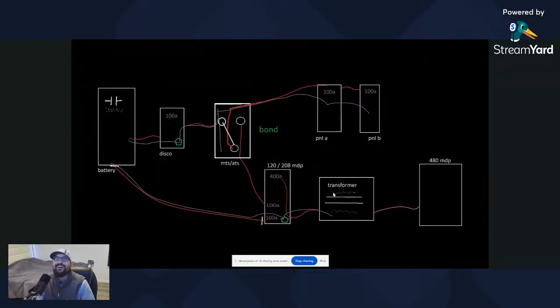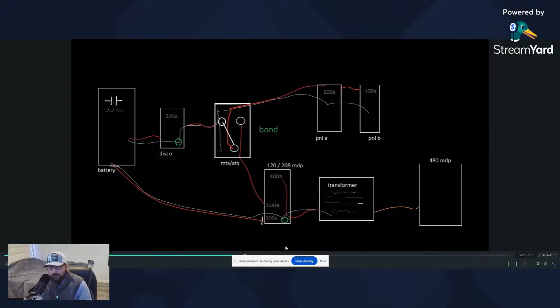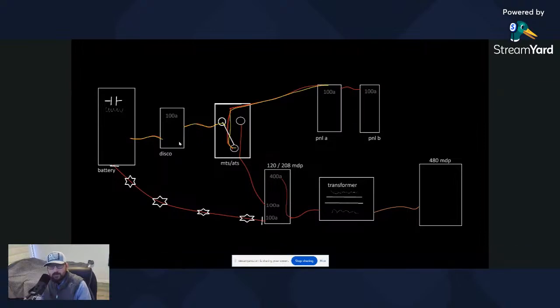All right, so we needed to add this disconnect, one, so we can create a spot to bond, because we need to bond at our first means of disconnect. We need to bond where all our neutrals come together. This is where you bring your building steel to. This is where your grounds and neutrals would bond. And this is pretty much your service, because if this is all off, which it is, we go back here, this is dead. So we no longer are using the neutrals over here. We've created the neutral here. So this is where you want to bond, because where your neutral's created, this is where you get current back to the source. So we bonded in this disconnect.